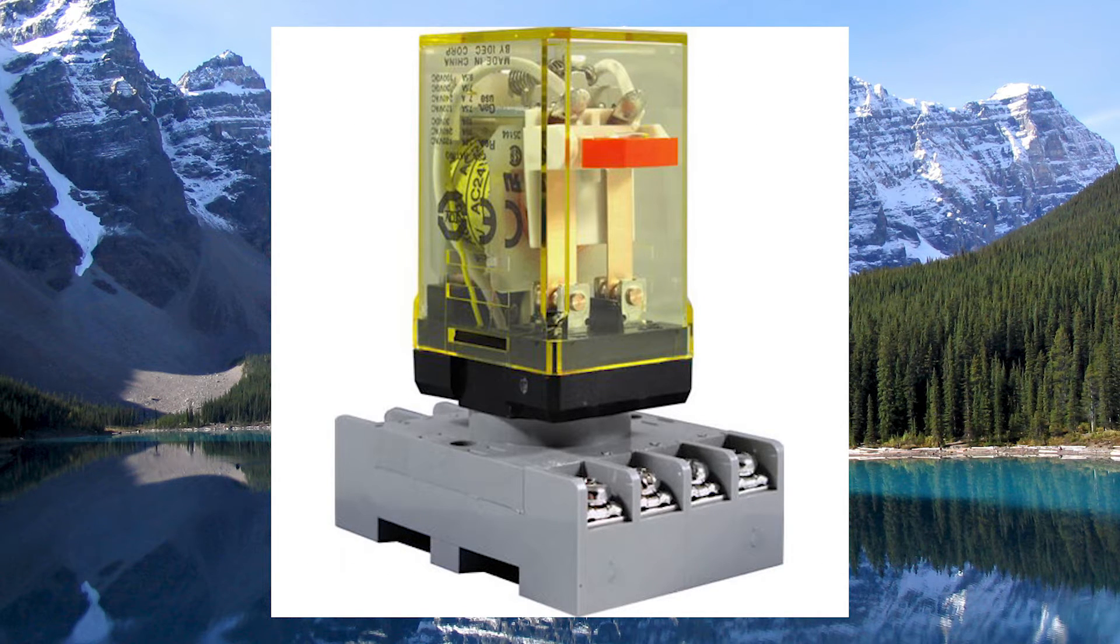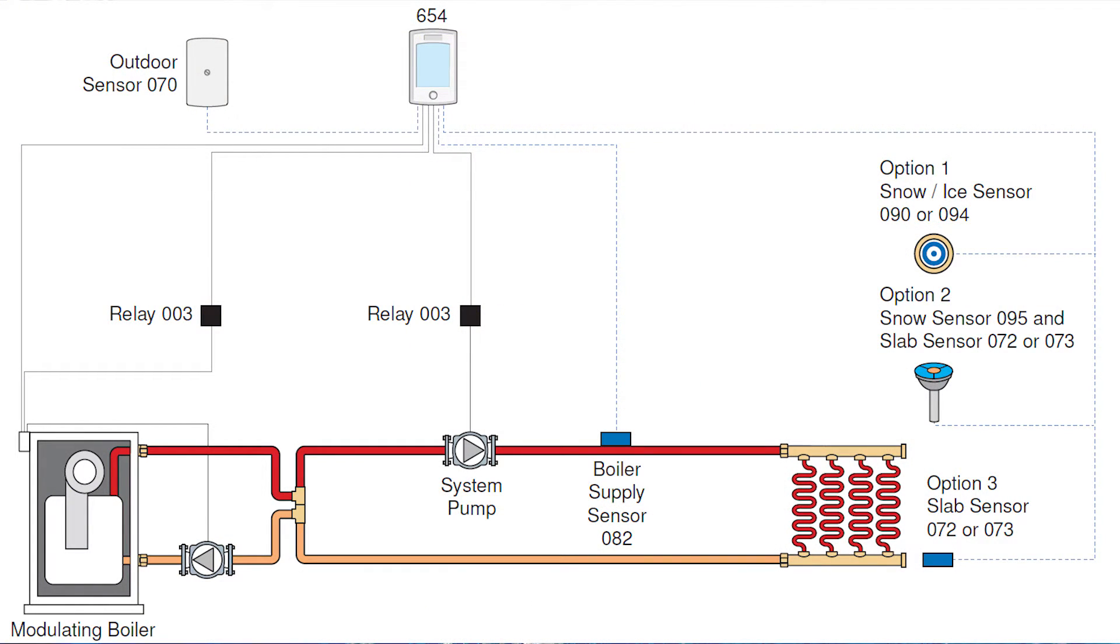Now I will not be going into great detail on how a relay works in this video, but the idea would be I have a 24-volt transformer with a 24-volt thermostat, and I run a wire from that to a relay. Now on the other side of this relay is a 120-volt pump, so I can use this 24-volt transformer and thermostat to power up a 120-volt pump. Whereas if I just did it directly and wired 120 volts to my thermostat, the thermostat would disappear in a great puff of smoke, and it would be very bad.